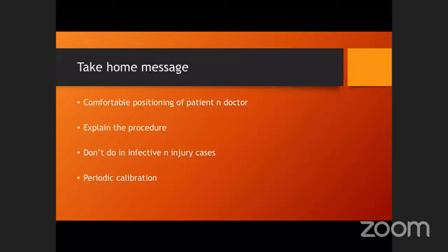So my take home message would be, before taking this IOP, we have to have a comfortable positioning of the patient and doctor. The procedure should be explained well to the patient. We must not do it in infective cases or in injury cases, and a periodic calibration of the Goldmann Applanation Tonometer is a must to have an accurate result.